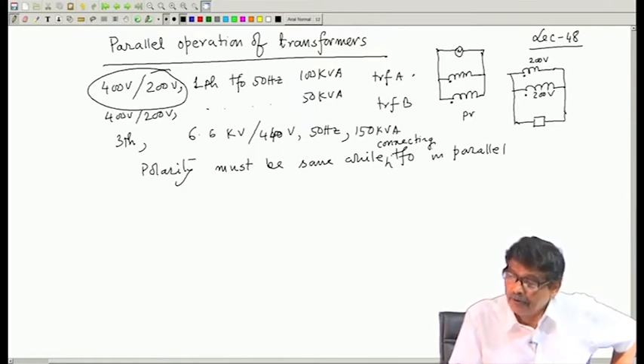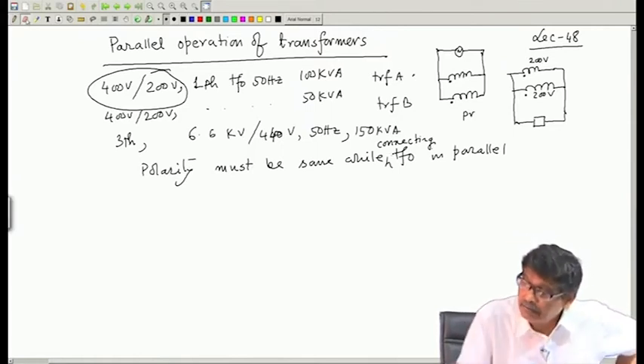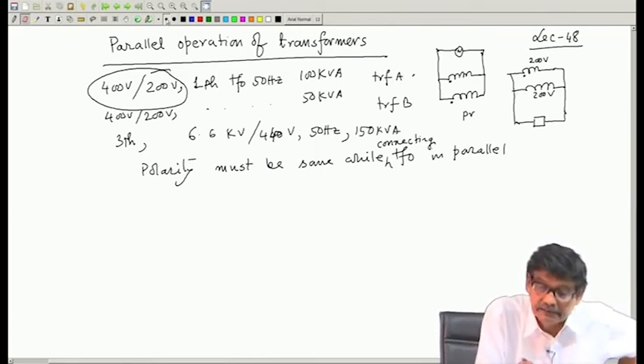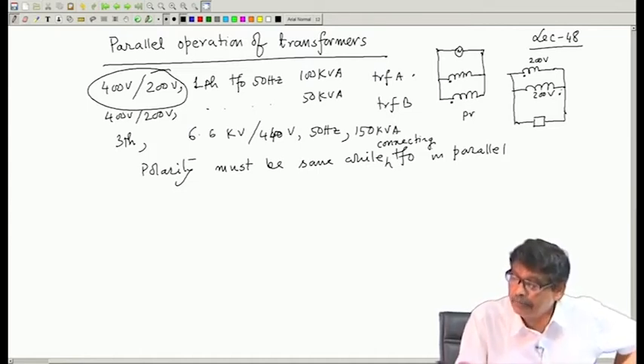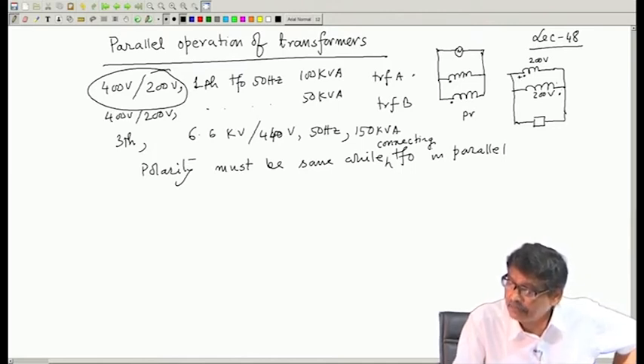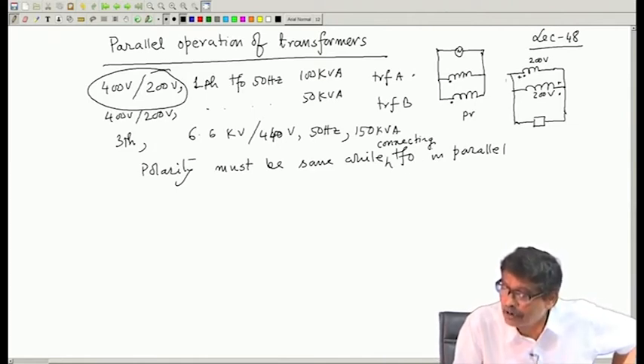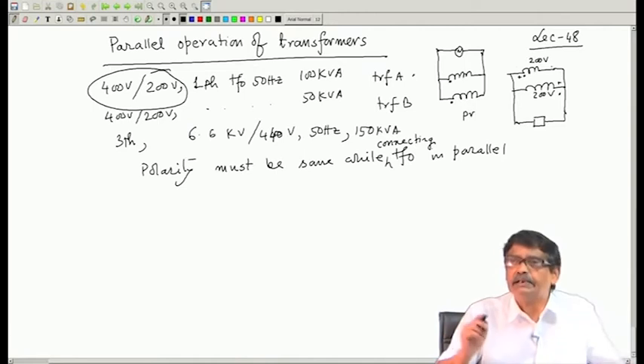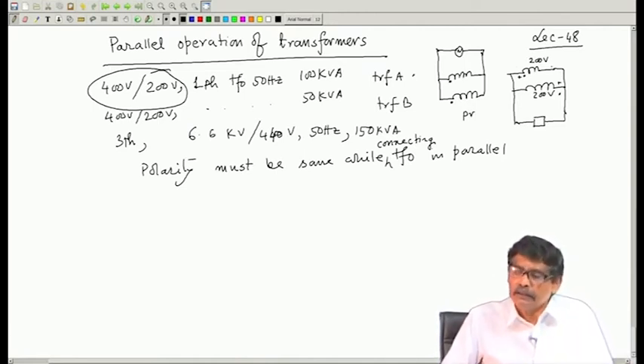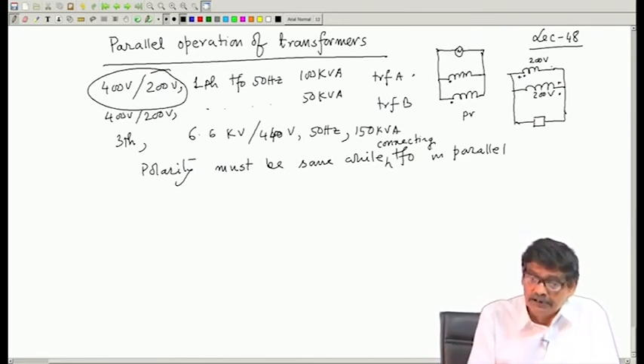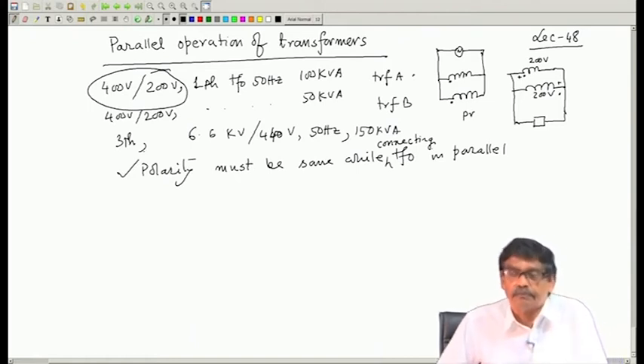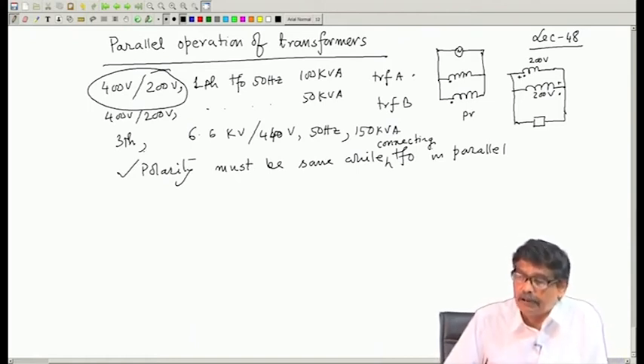If somebody connects the secondaries by mistake like this, then what is going to happen? The dot becomes plus 200 volt, and here the dot also becomes plus 200 volt. The load you have connected will find 400 volt acting in the circuit, creating a huge current. It is equivalent to a short circuit. So this should be avoided, it is not allowed at all. Polarity is a must condition before you connect transformers in parallel.